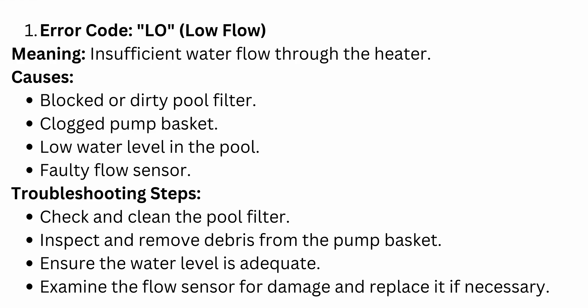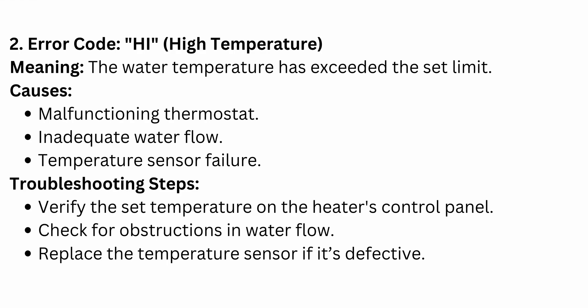The first error code is LO — its full form is Low Flow, meaning insufficient water flow through the heater. Causes can be a blocked or dirty pool filter, clogged pump basket, low water level in the pool, or a faulty flow sensor. To troubleshoot: check and clean the pool filter, inspect and remove debris from the pump basket, ensure the water level is adequate, and examine the flow sensor for damage and replace if necessary.